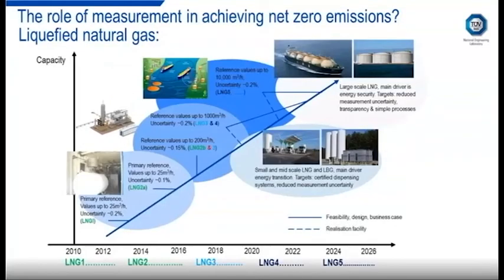So in terms of the development, in terms of operating ranges, they started with a small system based on a primary reference flow standard with flow rates of up to 25 meters cubed per hour and an uncertainty of 0.2%. Over time, towards the LNG3 project, the uncertainty has been reduced and the reference flow rates have been increased. So there's now a maximum flow rate of 200 meters cubed per hour and an uncertainty of 0.15% at the VSL facility. And the aim is to keep improving on this and develop new facilities which are ultimately traceable to the primary standard developed by VSL.